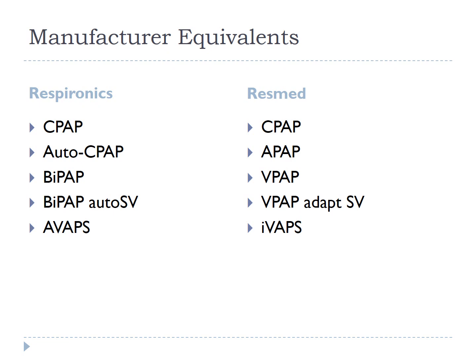We have one more type of machine out there. This machine has 2 different pressures, and the goal is to maintain a tidal volume and minute ventilation. These machines adjust the pressure support to maintain a goal tidal volume or minute ventilation depending on the manufacturer. So Respironics' name for this machine is an AVAPS, and ResMed's term for this machine is an IVAPS. Let's go on.